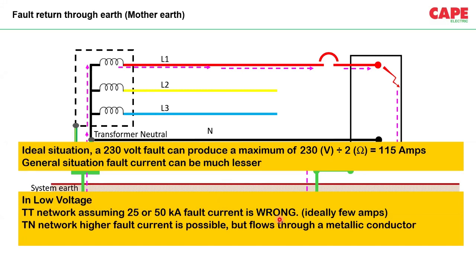Number two, in a TN network, higher fault current is possible. Of course, 10 kiloampere, 25 kiloampere, 50 kiloampere may be possible. But you should understand that that particular fault current is flowing through a metallic conductor. It is not going to flow through the earth electrode in soil. Of course, the amount of current which is going to flow through the earth electrode may be very, very less, a few milliamps or very less. Majority of the current flows through the metallic conductor.